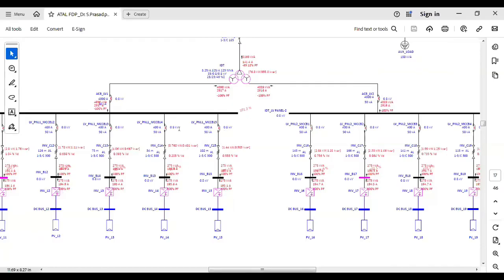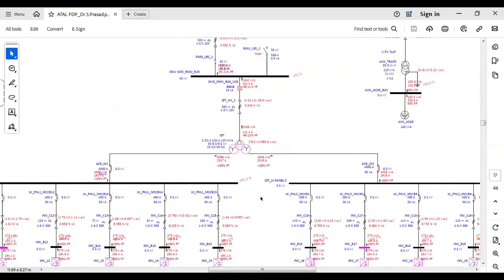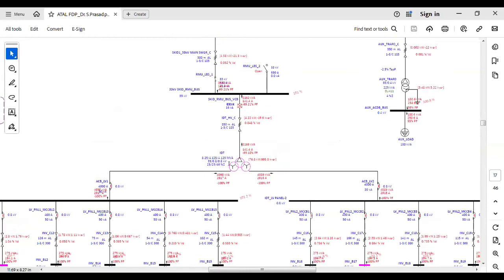Since it is a three winding transformer, two LT panels are there. In each LT panel there are 15 inverters of capacity 275 kVA. So 15 plus 15, which is 30, into 275. This is the total kVA rating of the PV plant, at around 8.25 MVA, and the IDT transformer rating is 8.25.